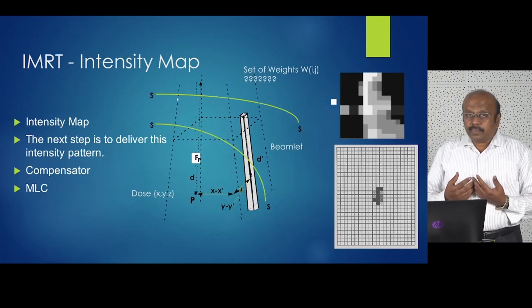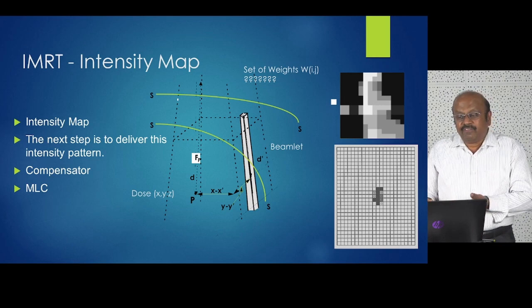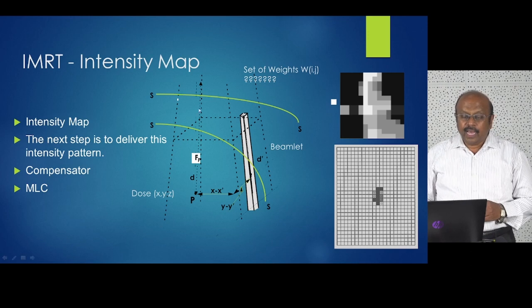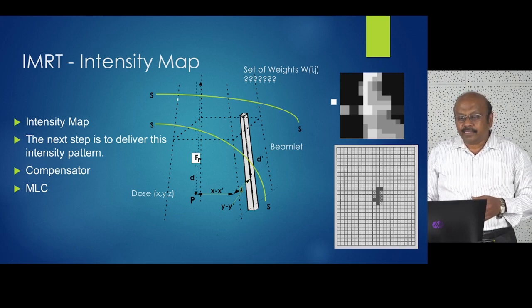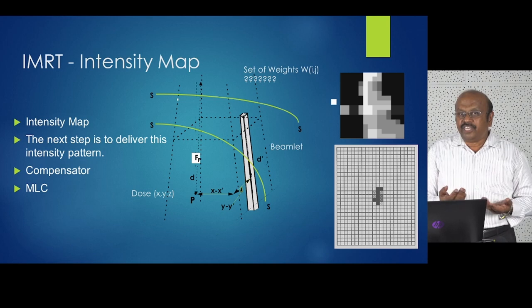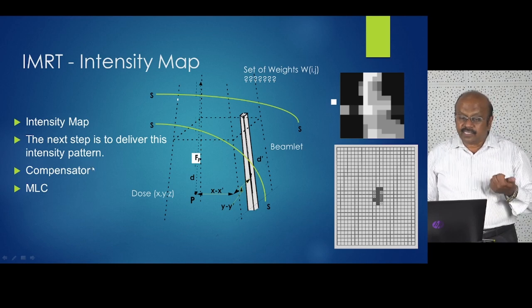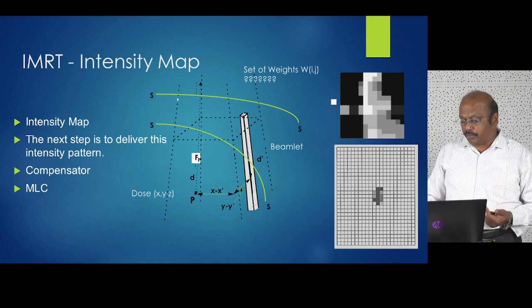Now you have obtained an intensity map through optimization. You have to deliver this intensity map. When using a multi-leaf collimator, you define beamlets — the width of the beamlet corresponds to the width of the multi-leaf collimator leaf. The length can be changed depending on the type of delivery. To deliver this intensity pattern you can use a compensator, which provides much smoother delivery, or you can use MLC.